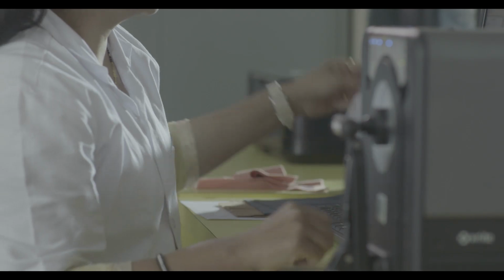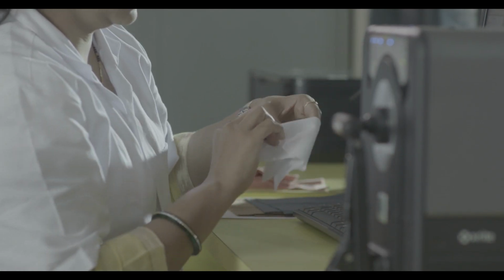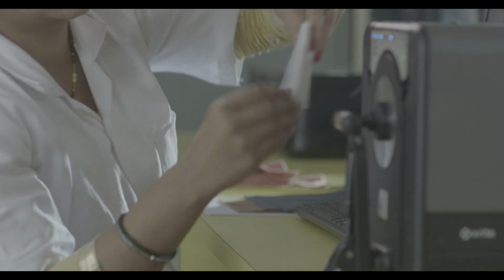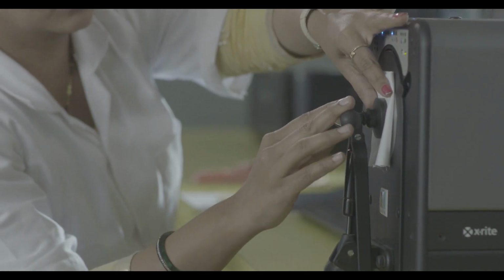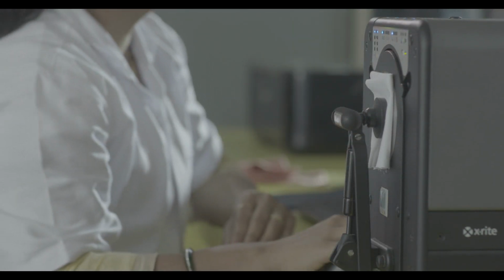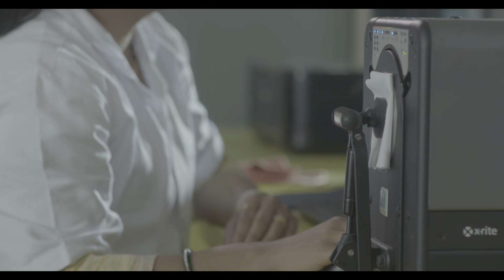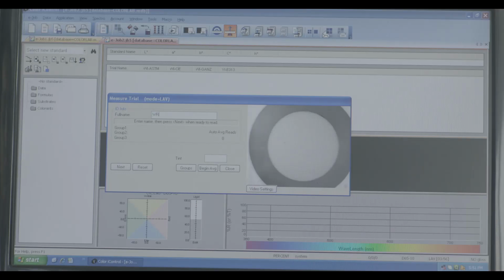Whiteness measurement. Open a new job. Take a test sample and fold it. Open the sample arm on the spectrophotometer to the fully open position. Present the sample at the viewport and slowly close the sample arm. Select Measure Trial. Name the sample and follow the software instructions for loading the sample at the viewport. Take multiple readings as per requirement.